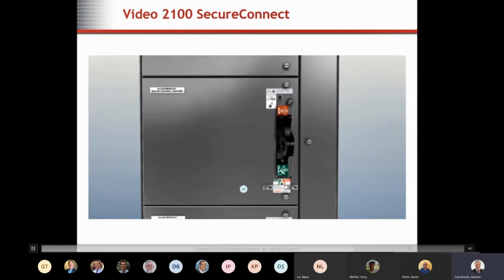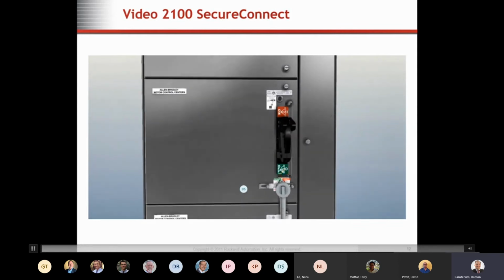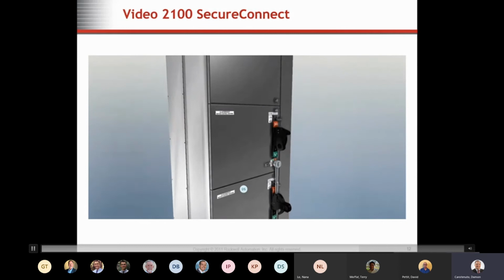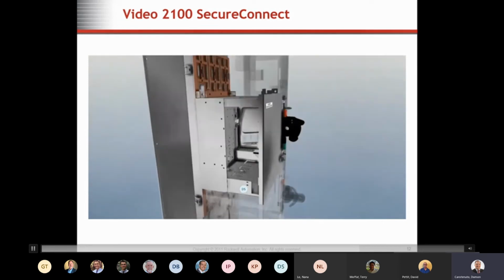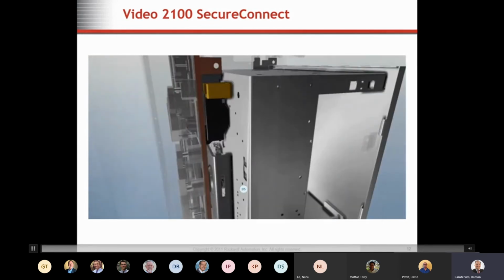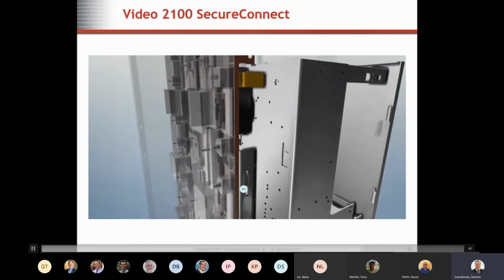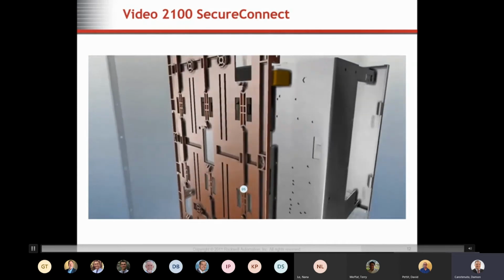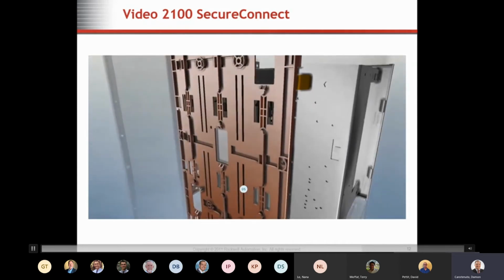First, turn the unit disconnect handle to the off position. This raises the actuator port window, which allows you to insert a standard socket wrench. Next, simply turn the wrench a 1/4 turn and the unit stabs will be disconnected from the vertical bus. As the stabs disconnect, they rotate up and into the unit housing. At this point, the unit power stabs, control, and network wiring have all been disconnected. All of this while the unit door is closed.